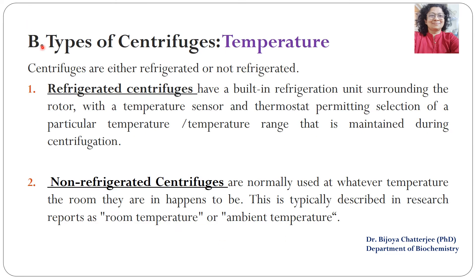The second classification is based on temperature. A centrifuge can be refrigerated or non-refrigerated. Refrigerated centrifuges have an inbuilt unit surrounding the rotor with a temperature sensor and thermostat, allowing selection of a required temperature range. Very high speed or ultracentrifuges are generally refrigerated. Non-refrigerated centrifuges are used at room temperature, described in research reports as ambient temperature.